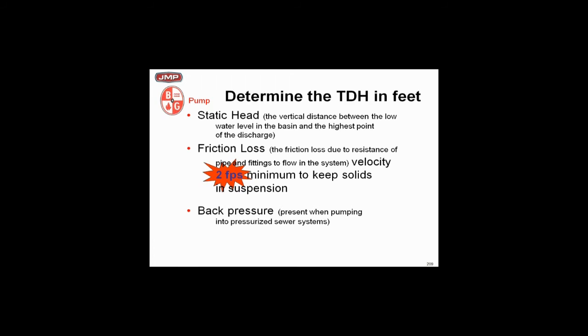So there's all kinds of little things you got to deal with, but we got to do the pump head calculation exactly, precisely because you cannot throttle these pumps. Remember, full open gate valve on the discharge. You're not allowed to throttle the valve. You're not allowed to balance these pumps.